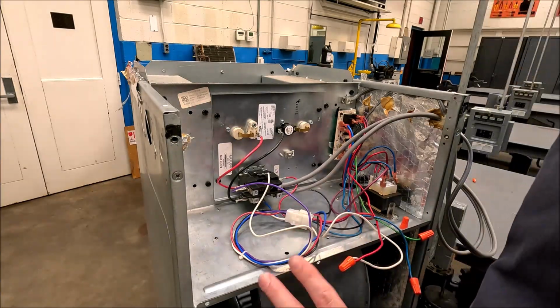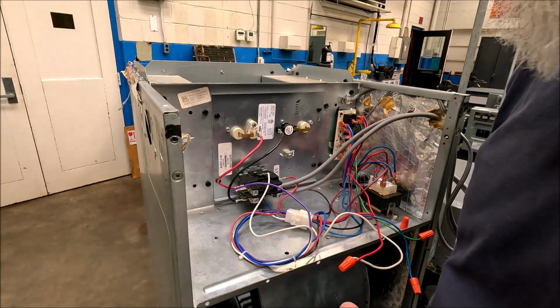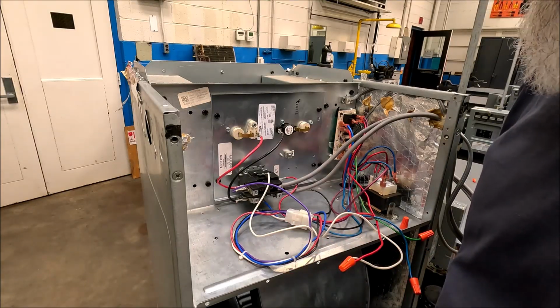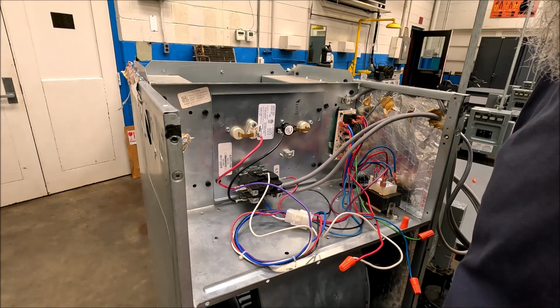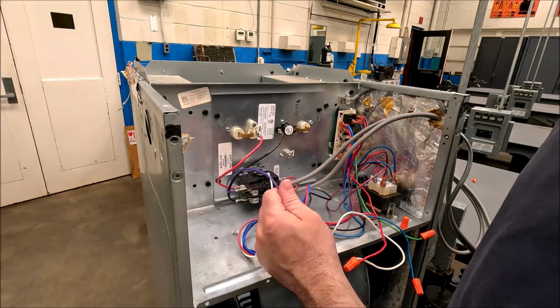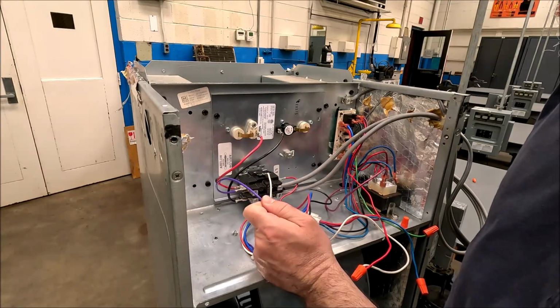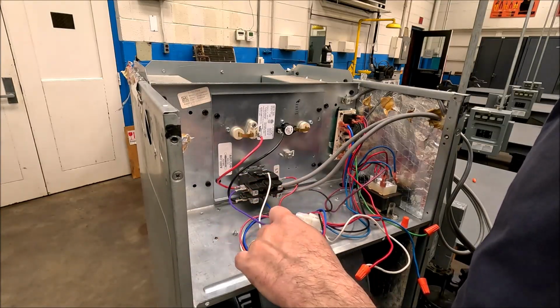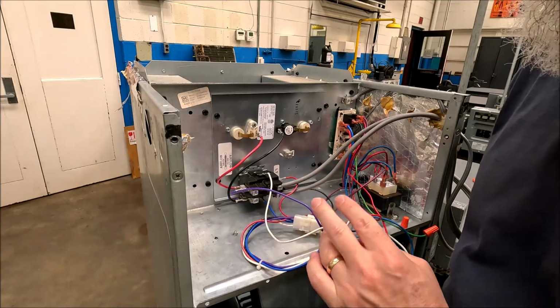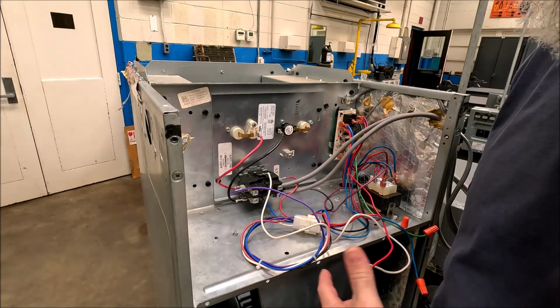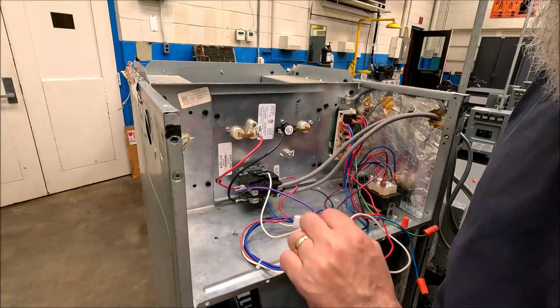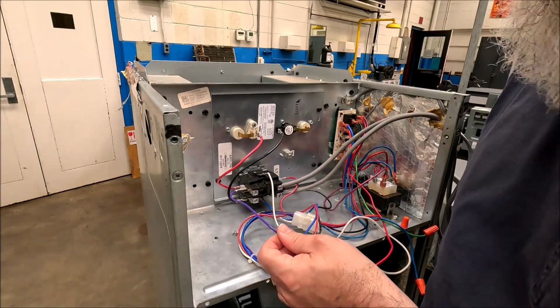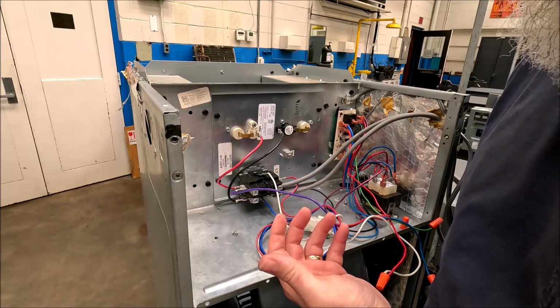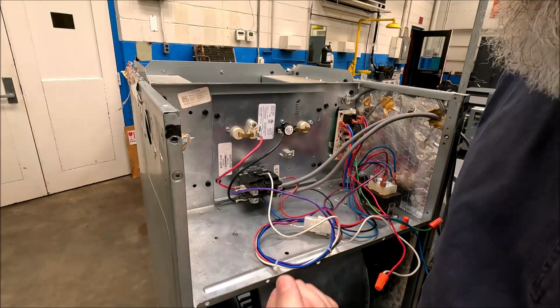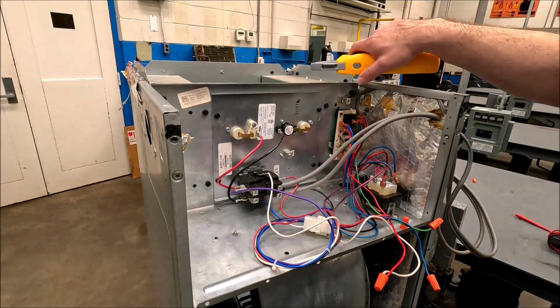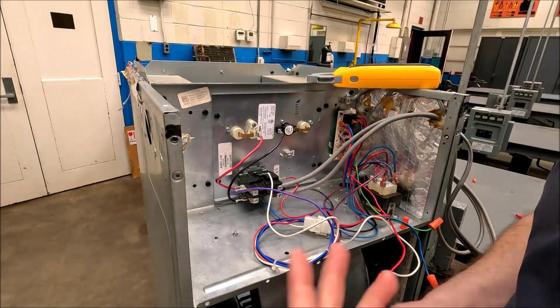Now for a PSC motor, because you've got 2 windings inside, and I'll show you one more setup where hopefully you'll see it better. But just because you check the amps on one wire, we know it's powering there. Sometimes because of those 2 windings and the relationship that they have and the resistances and the different amp readings, the amps you get on this wire may not be what would be the total motor.